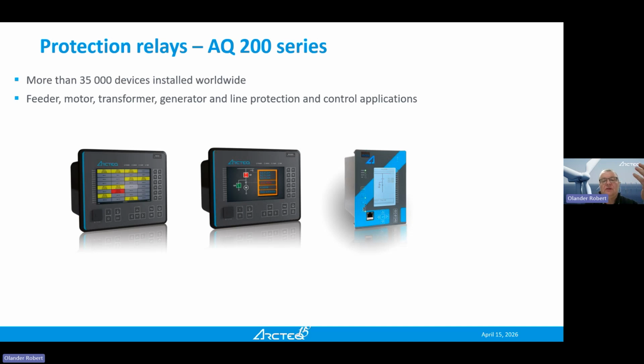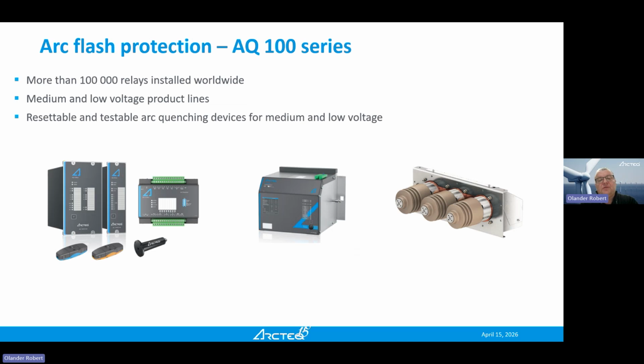So protection relays, we call them the AQ200 series. We have different setups there, with slightly different hardware depending on the need and how much I/O is needed. Then arc flash protection, our other big leg. There we have a much more significant role globally than in protection relays, which is quite competitive. But here we are actually the only one who can provide a solution with a quenching device which fully meets the IEC specifications. I will explain more details about that also.